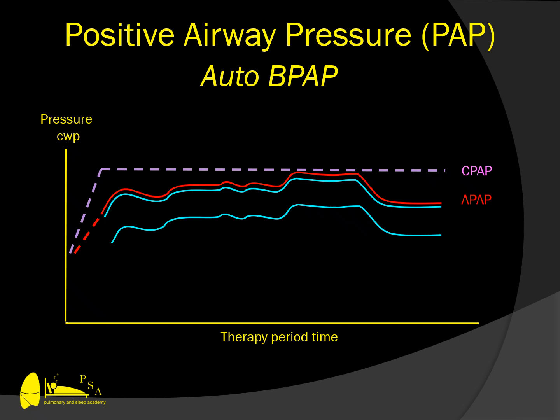The option then would be an automatic BiPAP unit or titrating the patient in the lab and finding a fixed pressure BiPAP. But BiPAP is going to comprise a higher pressure that's delivered during inspiration and a lower pressure that can be set specifically at, say, 4 centimeters of water lower, or a different value than 4. But typically 4 is a nice reduction that gives the patient relief when they're exhaling. And at the beginning of the therapeutic period, there can also be a ramp for that until it gets up to that pressure.